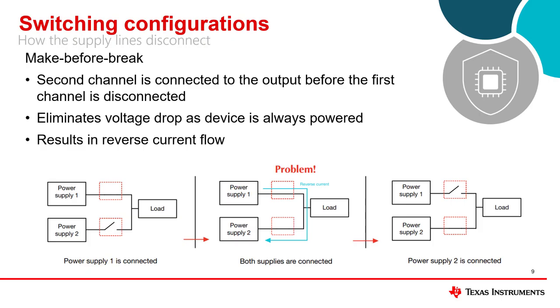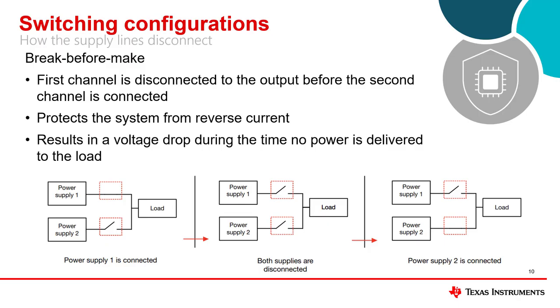There are two ways for the two supply lines to disconnect from the load. The lines can be in a break-before-make configuration or a make-before-break configuration. In a make-before-break, the second channel is connected to the output before the first channel is disconnected. As shown in the figure, this results in an issue of reverse current since both supplies are connected to the output at the same time. Instead, you can use a break-before-make configuration to ensure no reverse current flows through the device.